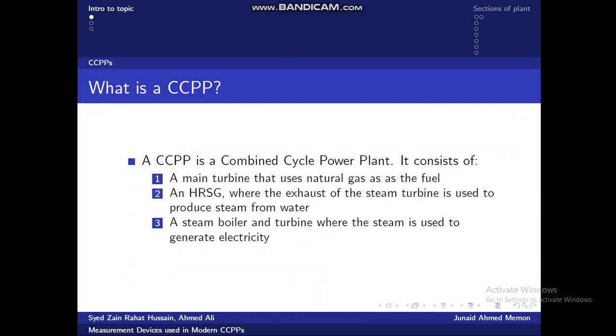So what is a CCPP? A CCPP stands for Combined Cycle Power Plant, which are basically generation stations that have both a gas turbine that is fired by natural gas, as well as a steam boiler and turbine that uses the hot exhaust gases from the gas turbine to boil water to generate electricity. So you might see something written here, which is HRSG, which stands for Heat Recovery Steam Generator, which uses the hot exhaust gases from the gas turbine to produce steam for the steam turbine. And this is primarily done to increase the overall efficiency of the plant.